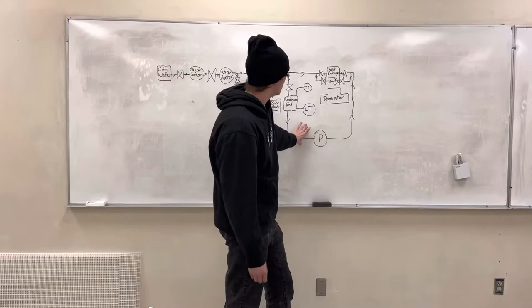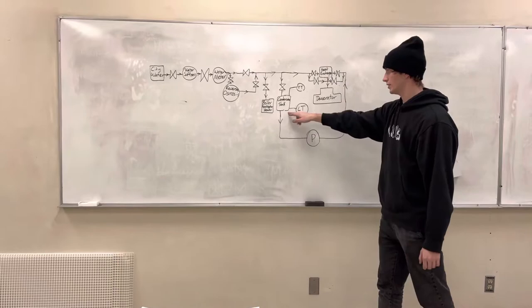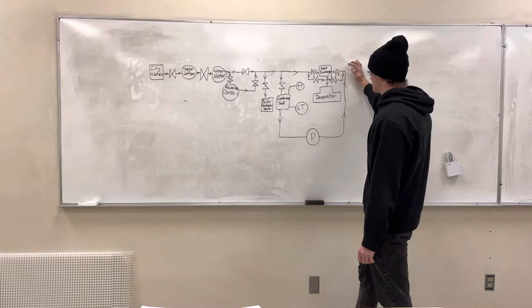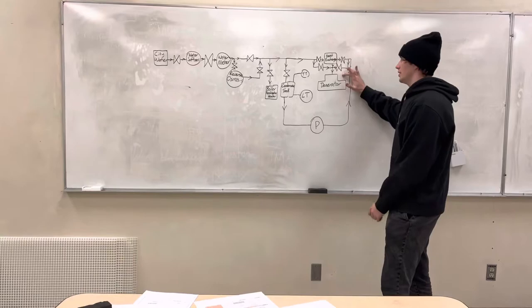Then it sends to the condensate pump which pumps it up to this heat exchanger, or you can bypass it if it's not hot water because it'll be sitting in there and get cold. So you can bypass it and go straight into the deaerator, or you can have it go into the heat exchanger and then the deaerator.